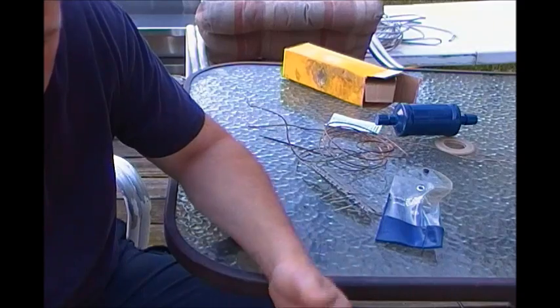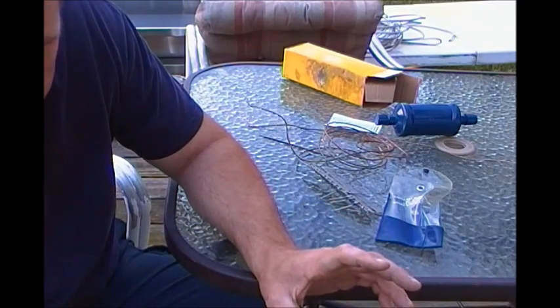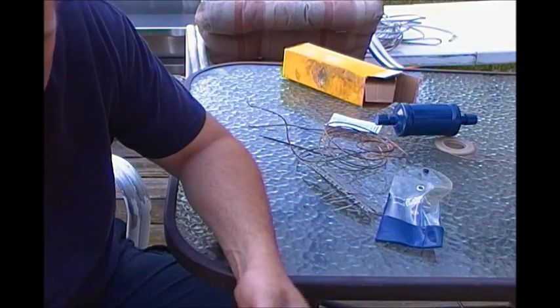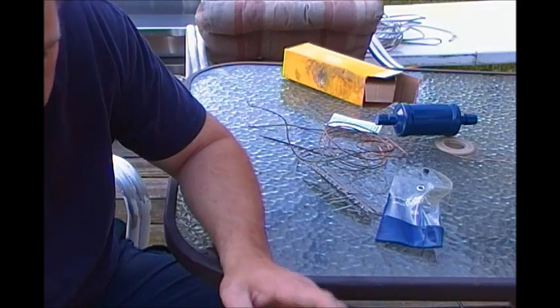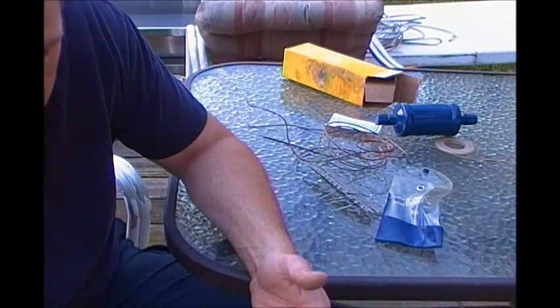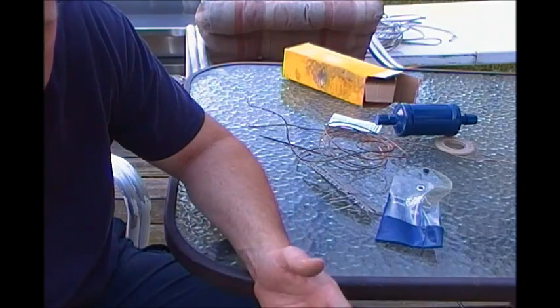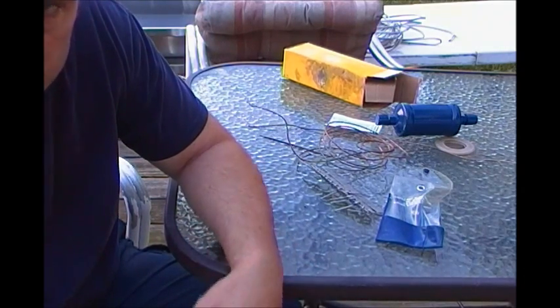Then you go inside the cooler. You open it up. You look on the plate and you see what kind of gas you're using. Now you know what horsepower you have and what gas type you're using. So you go back to RE Michaels. You look on that chart and it tells you exactly which capillary tube to buy and how long to cut it to put it on the unit. It's that simple.